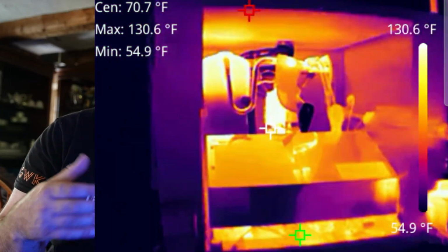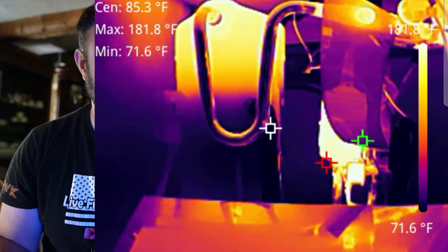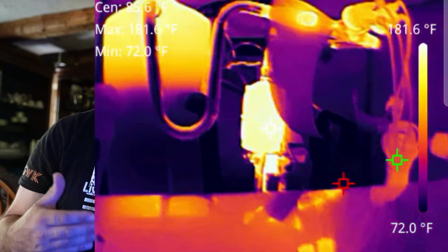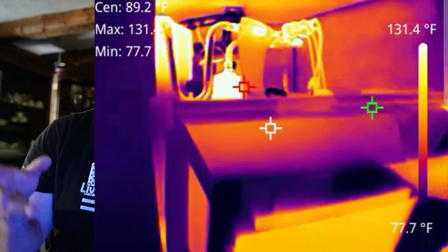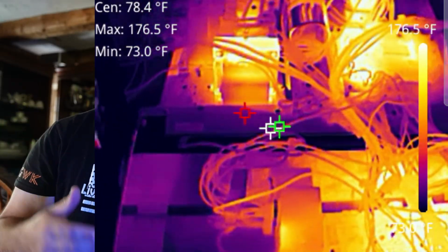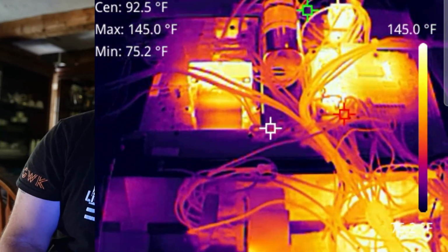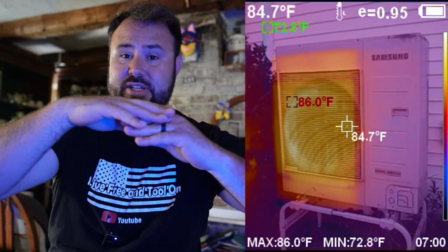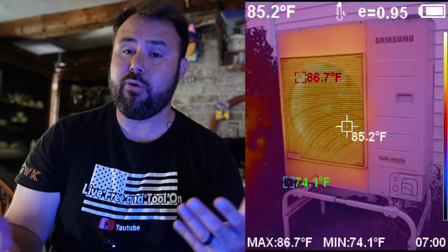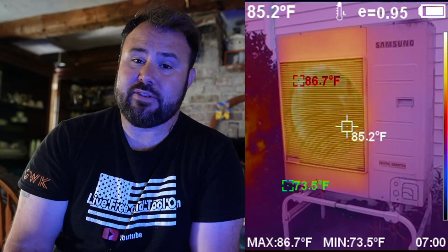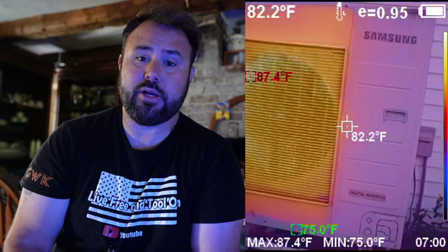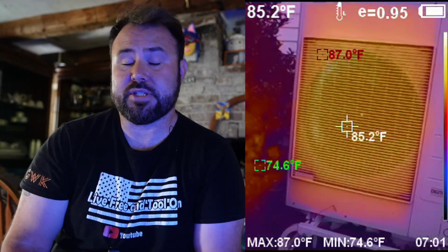Now check this out. What if you have a reversing valve or a solenoid? It's really good to know what the temperature of those solenoids and reversing valves are and the delta T across those, because that could indicate if you have a solenoid that has stopped working, so the slide valve inside of it is no longer working, or if you have a reversing valve which is failing as well. You can do a lot of different things in order to tell what that is.